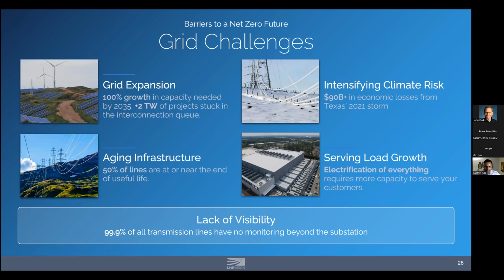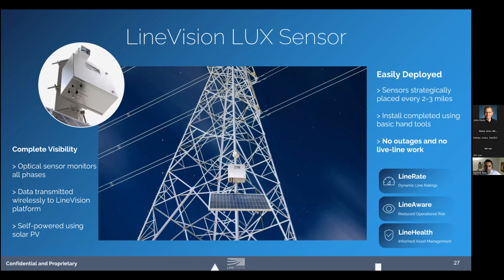If we can go to the next slide. So all of that starts with the sensor that we install. We have a sensor based on a technology known as LiDAR. LiDAR essentially shoots out points of light in all directions and times how long it takes to come back, creating a three-dimensional map of the surrounding space. We use LiDAR to look up at all three phases of a transmission line conductor and get really detailed understanding about the position of that conductor in space and time. This unlocks a whole bunch of valuable information about the conductor that can be used in a bunch of different ways, which I'll get to in a moment.